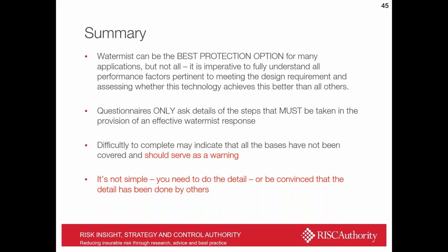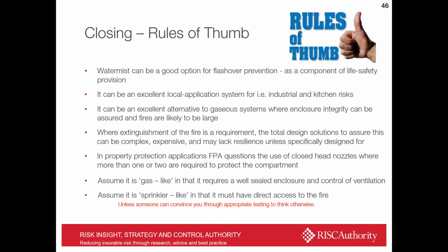That's all the grounds. It isn't simple. You do need to do the detail, or be convinced that the detail has been done by others. So I promised I'd leave you with a few rules of thumb, and these may be slightly controversial, but here we go. I'd probably sum up by saying that water mist can be a good option for flashover prevention as a component of life safety provision, and there are some very good domestic and residential applications for water mist, without a doubt.